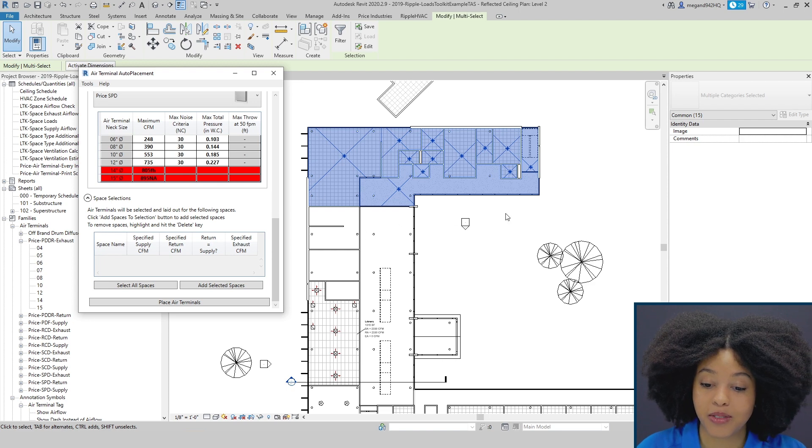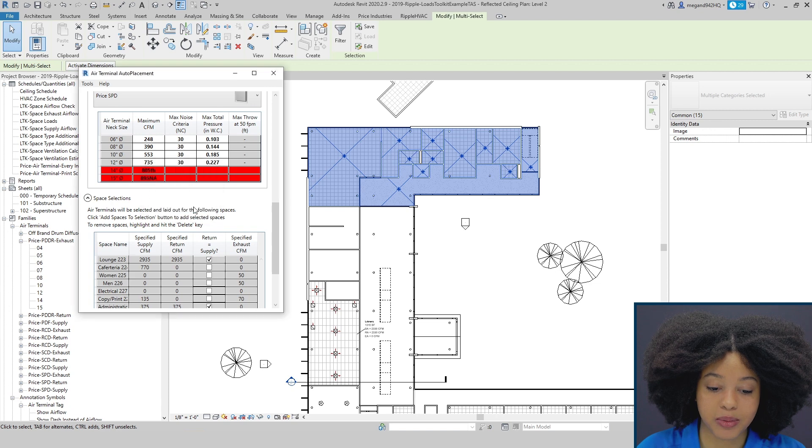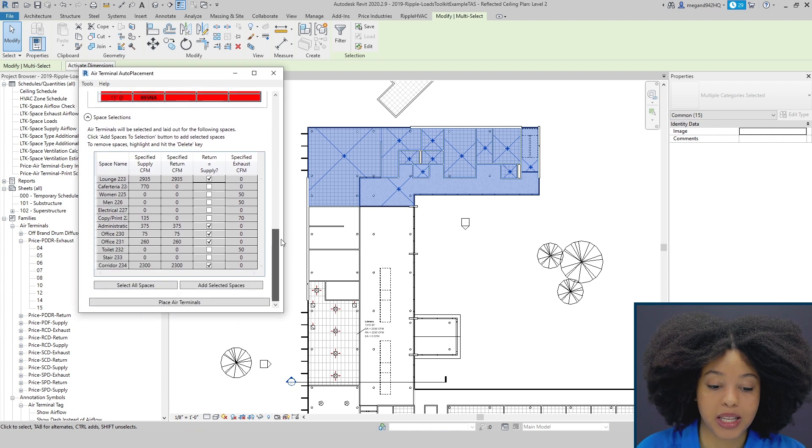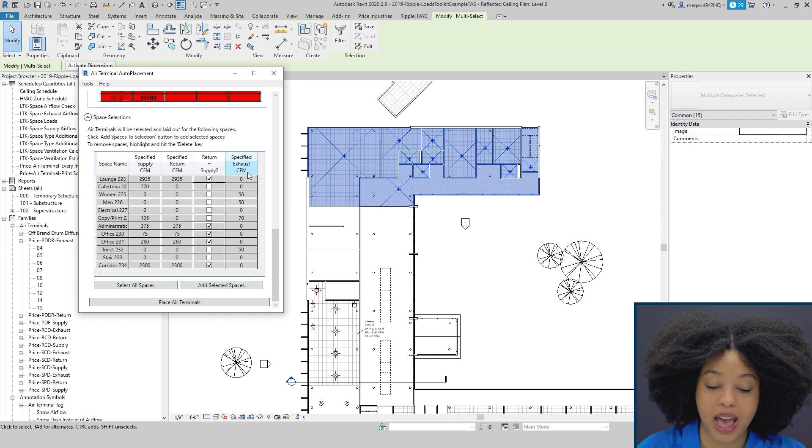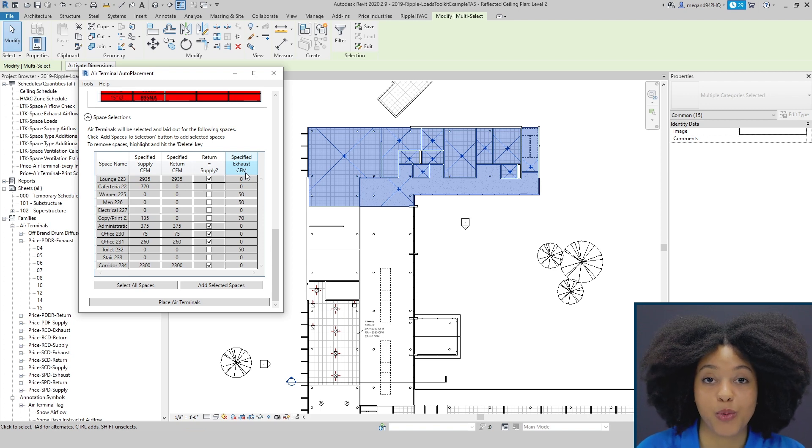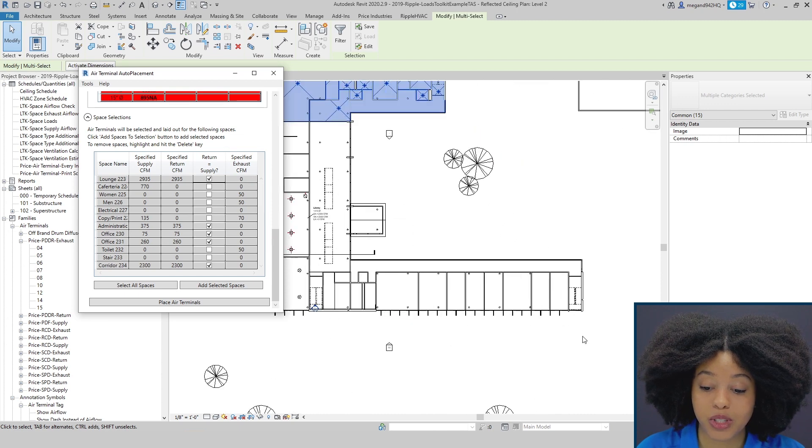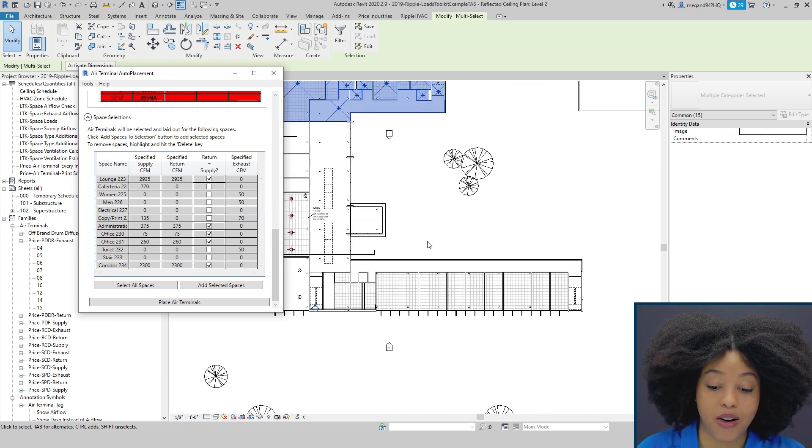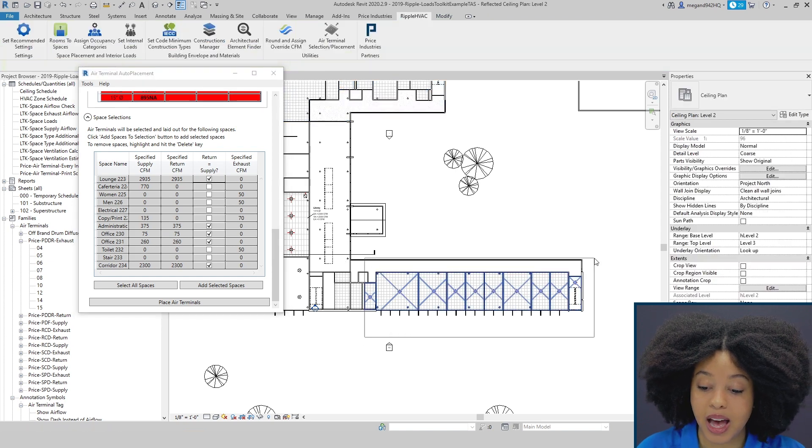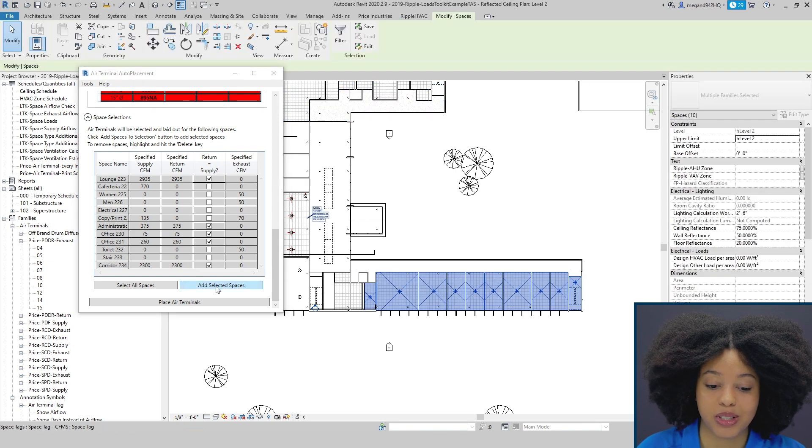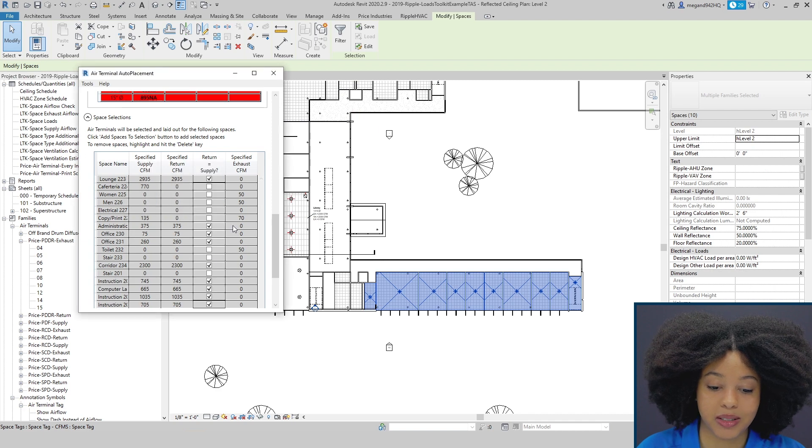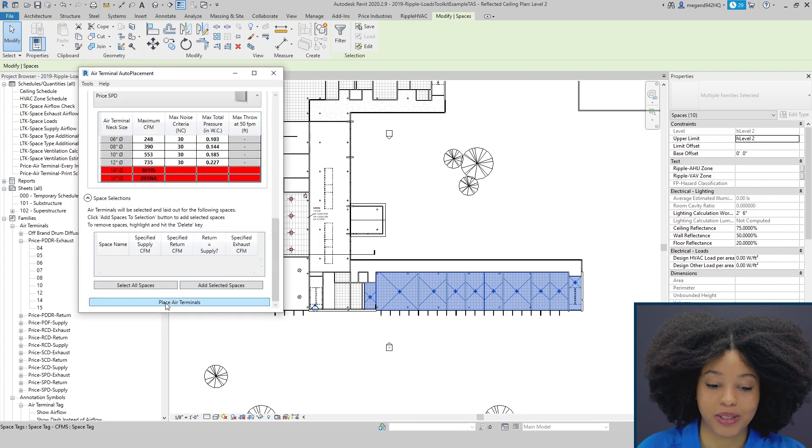Once we have our spaces selected, you can click add selected spaces. You'll notice that you'll see all the spaces in the tool with the specified supply, return, and exhaust. If there is no CFM within the room, then it simply won't place a diffuser there. If you want to select diffusers that are on different floors or levels or in different areas, you can simply highlight the other section and also select add selected spaces. Then you can place air terminals.